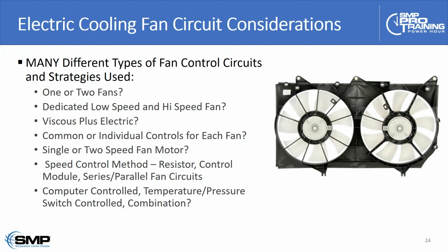Do you have one fan or two fans? Do both fans run in parallel, meaning do they both come on at low speed together, then go on to high speed together? Do you have a dedicated radiator fan versus a condenser fan? You can have several pressure inputs, the temperature inputs, and so on. The strategies and the components and the switches and the pressure transducers controlling fan speed can be quite complex. So you really have to sit down with your information system and look at the wiring schematic, look at pressure and temperature thresholds of various sensors and switches to really understand.